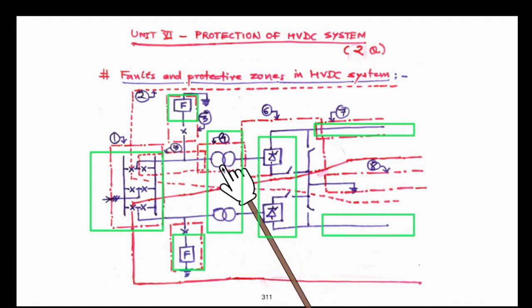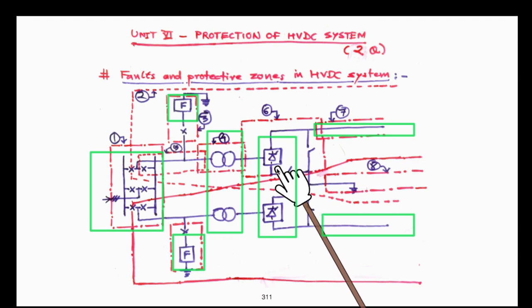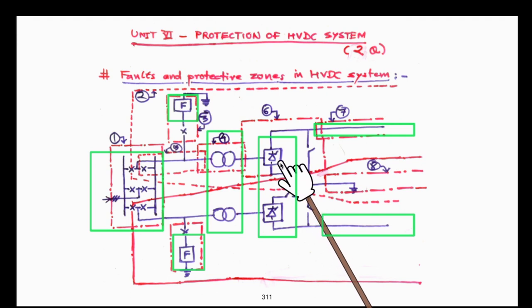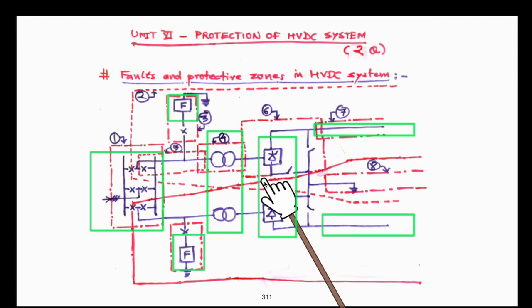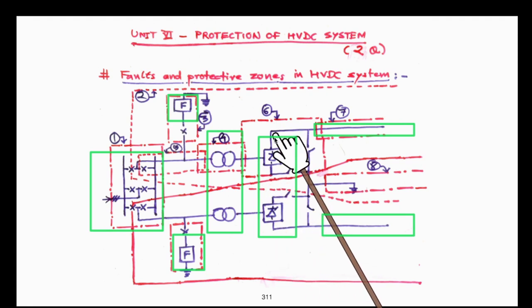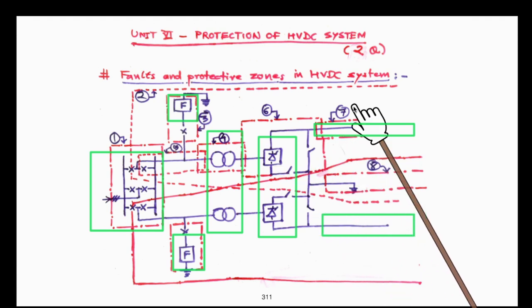There may be winding short circuit on the transformers, short circuit across the valve bridge legs or arms of the bridges, failure of the valve, misfiring of the valves, or failure in the conduction pattern of the valves — thyristors may not conduct in proper sequence. All these conditions are classified as faults and they may lead to development of conditions which will disturb the power flow and have to be rectified at the earliest.